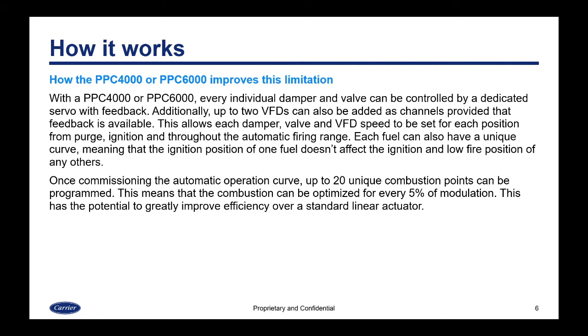Once commissioning the automatic operation curve, up to 20 unique combustion points can be programmed, which means that the combustion can be optimized for every 5% of modulation. This has the potential to greatly improve the efficiency over a standard linear actuator.